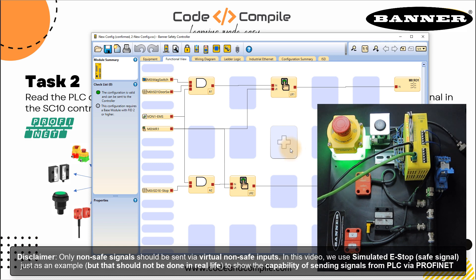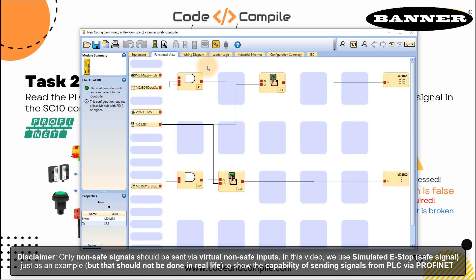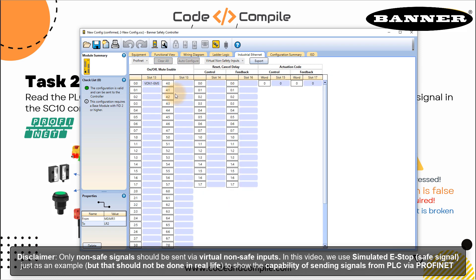Now let's have a look — I go to live mode, and you can see this is not true. One more thing I forgot to mention: we took the input here, but we also have to configure the flag in the Ethernet configuration. I have to go offline, then go to industrial Ethernet and go to virtual non-safety input. Here we define where we're going to read it. You can see it's automatically connected to my first output — VON, VON1, EMS. This is the input of the SC10 controller but the output of the PLC, so it's automatically coming here. If it's not there, you have to check where to place it.